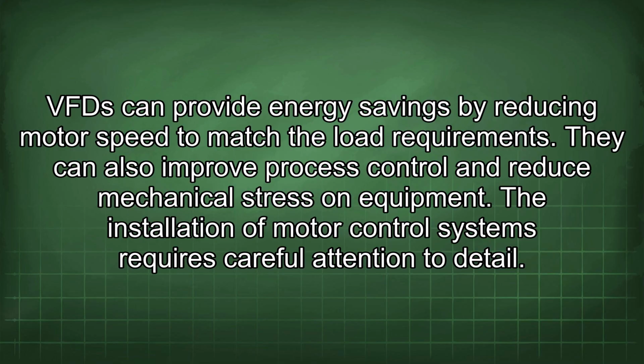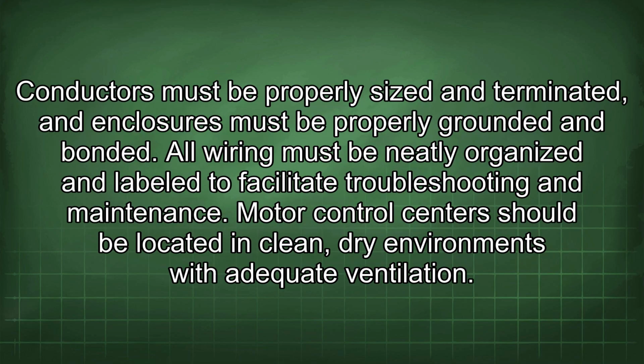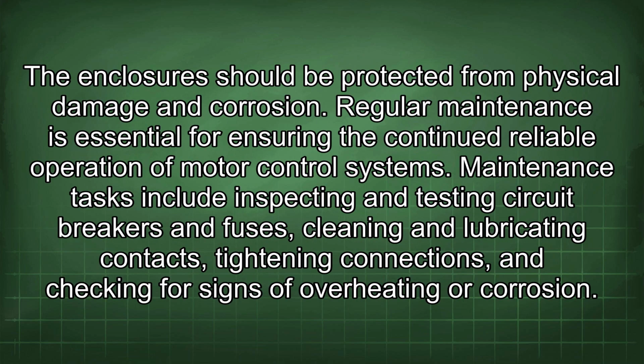The installation of motor control systems requires careful attention to detail. Conductors must be properly sized and terminated, and enclosures must be properly grounded and bonded. All wiring must be neatly organized and labeled to facilitate troubleshooting and maintenance. Motor control centers should be located in clean, dry environments with adequate ventilation. The enclosure should be protected from physical damage and corrosion.